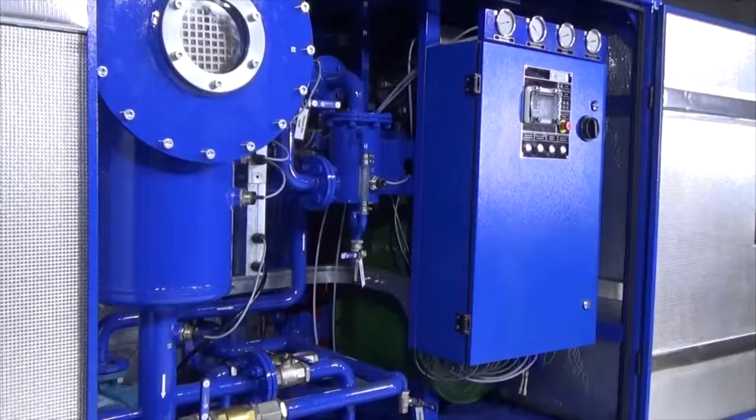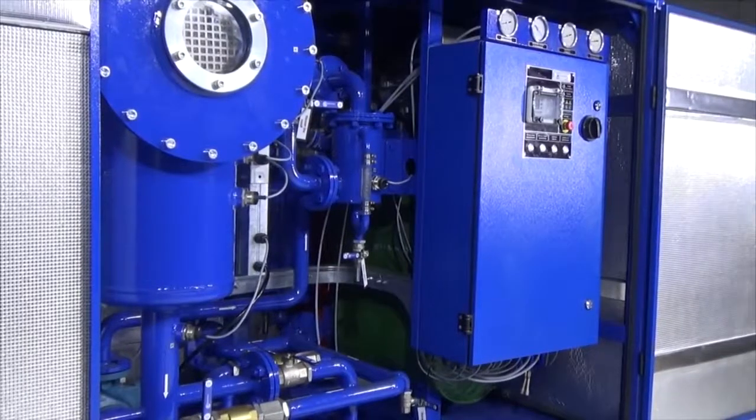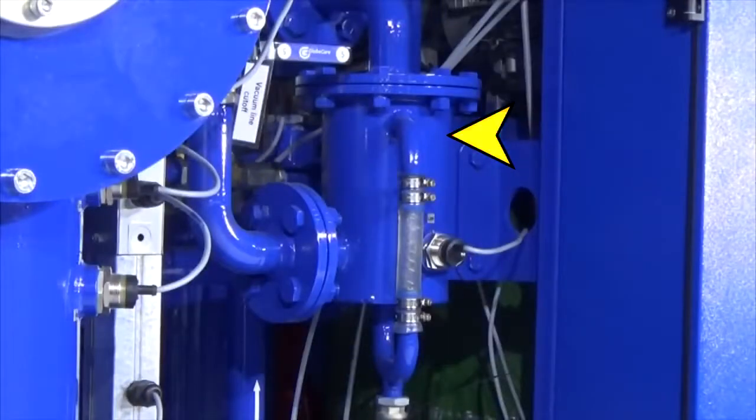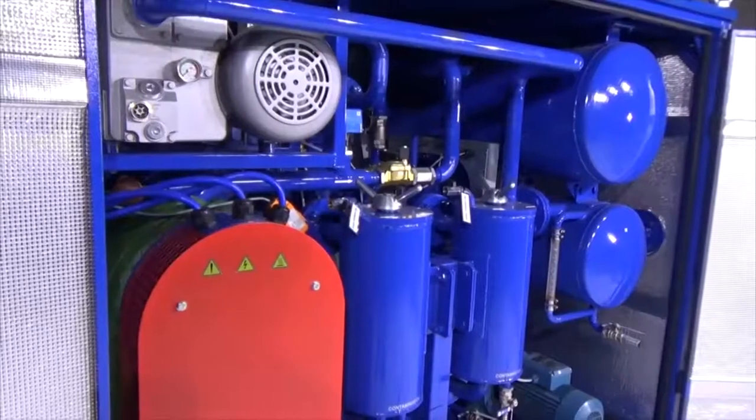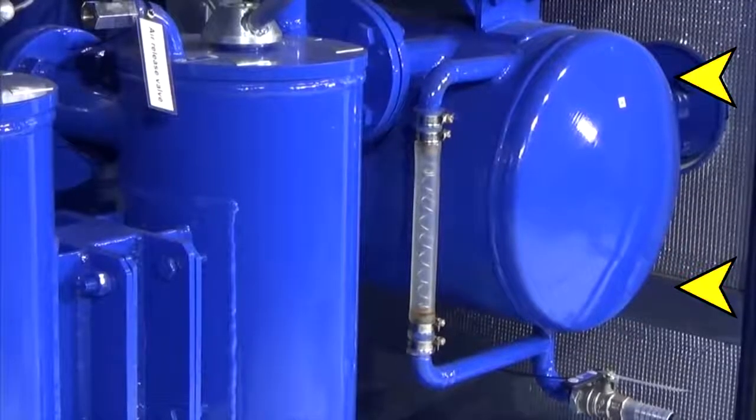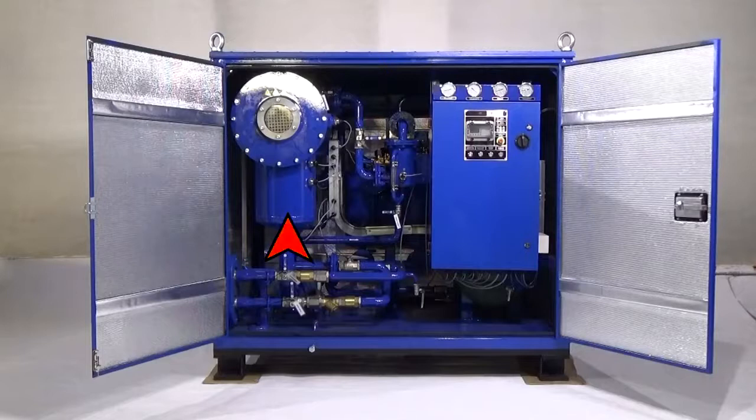Vacuum reduces the partial pressure of water, causing rapid evaporation. Moisture passes through the oil trap and the vacuum pump into the condensation vessel, where it accumulates for subsequent disposal. Processed oil accumulates in the bottom of the vacuum chamber.